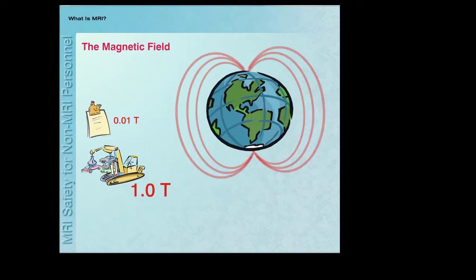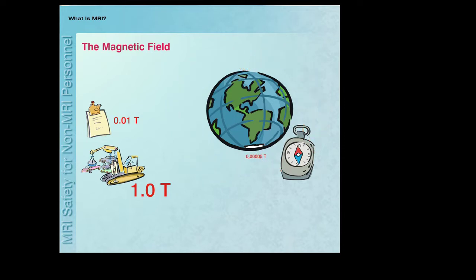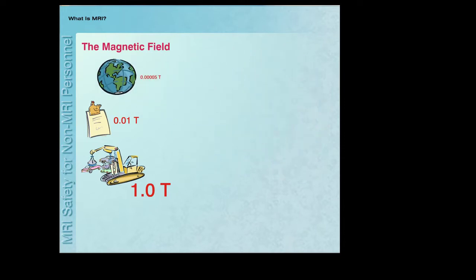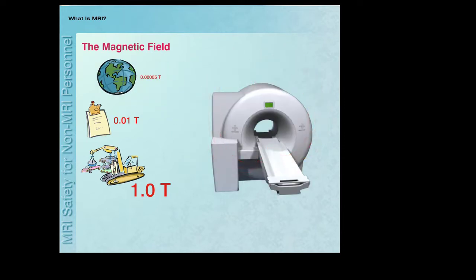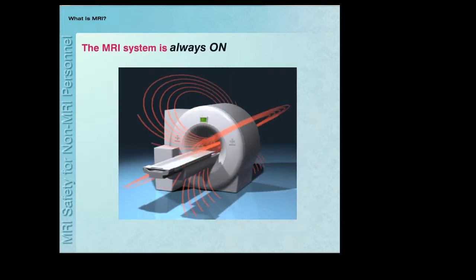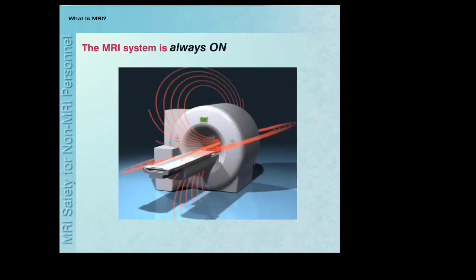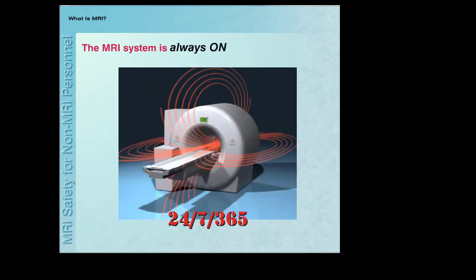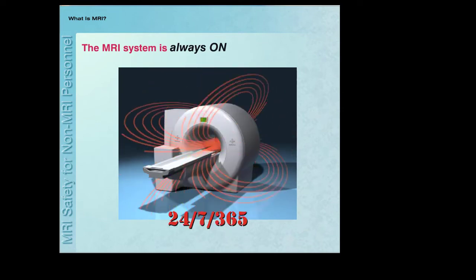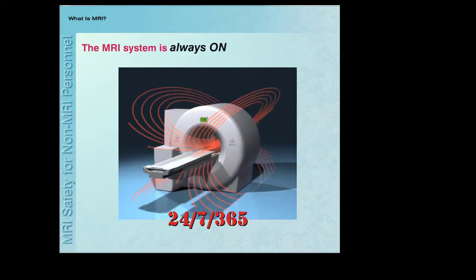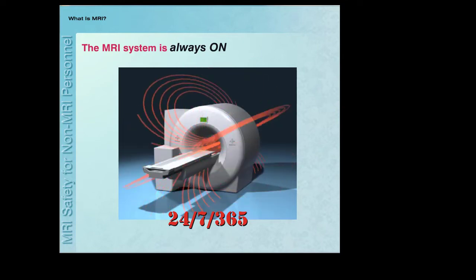The magnetic field of the Earth, which is responsible for making a compass needle point north, is very small. By comparison, the magnetic field strength of a typical MRI system, which is measured at 1.5 or 3 Tesla, is 30 to 60,000 times more powerful than the magnetic field of the Earth. Again, it is important to remember that the magnetic field of the MRI system is always on, 24 hours a day, 7 days a week, 365 days a year, even when a patient is not being imaged.